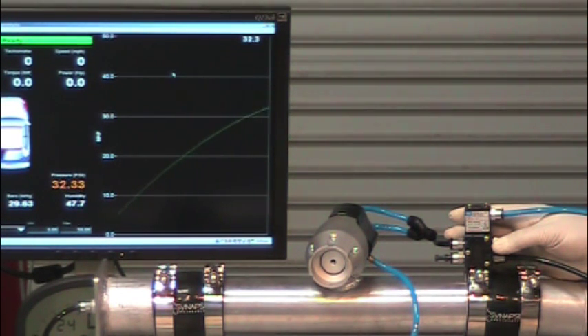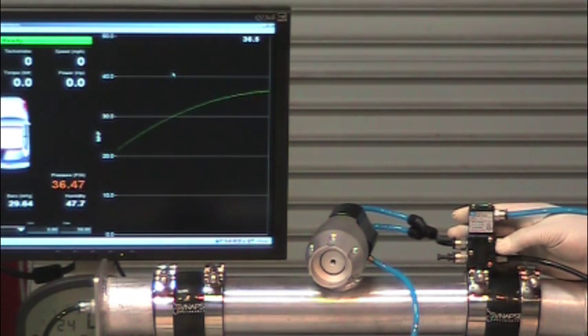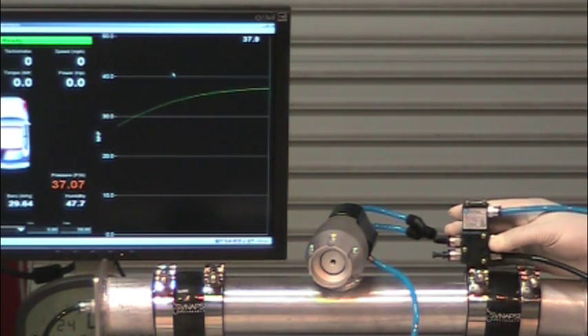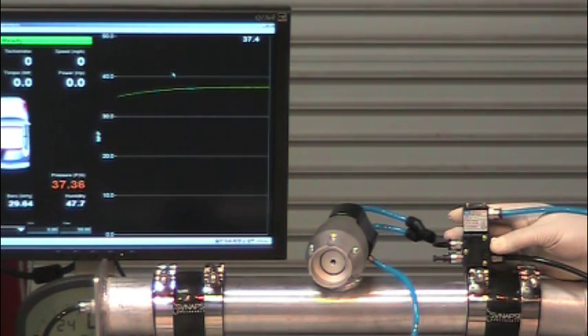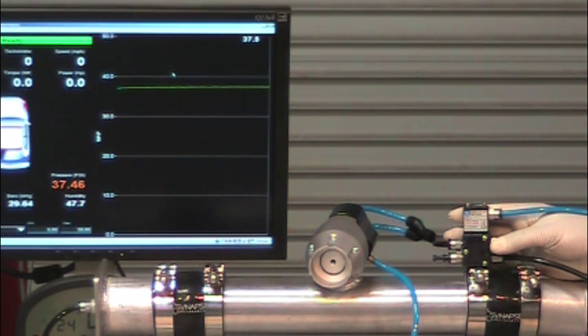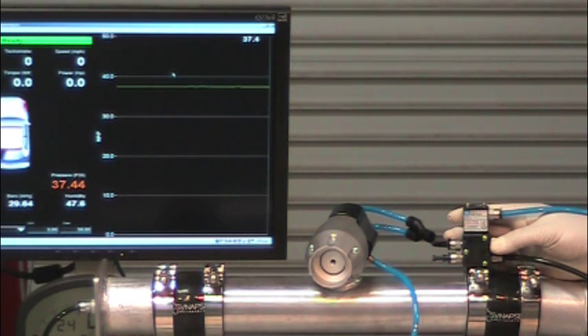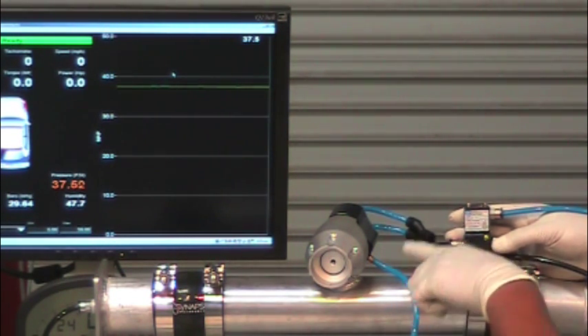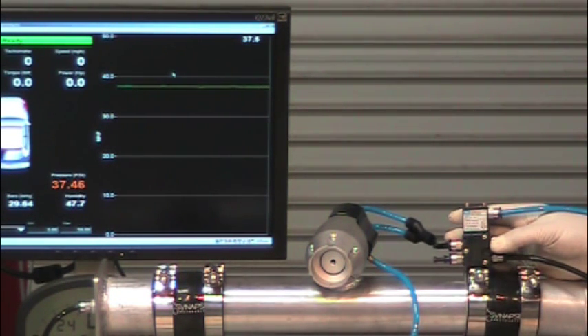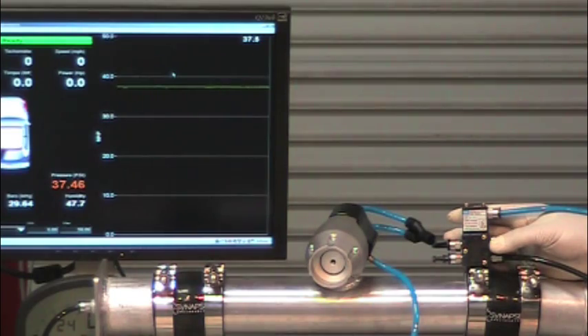The key here is we're able to actuate a pressure relief valve with only pressure, A, B, using the same system pressure. No pressure regulation on either side of the valve. The valve is actuated by the same pressure.